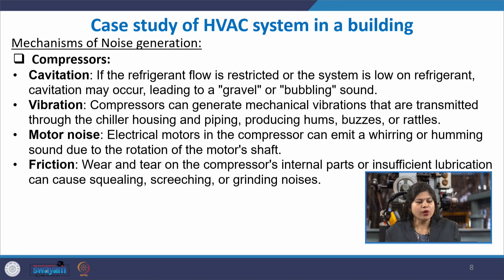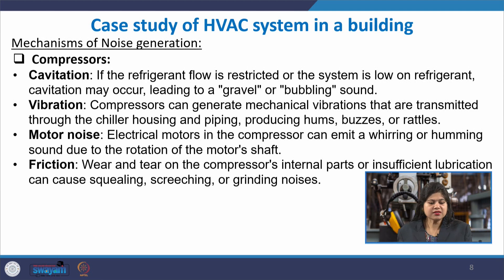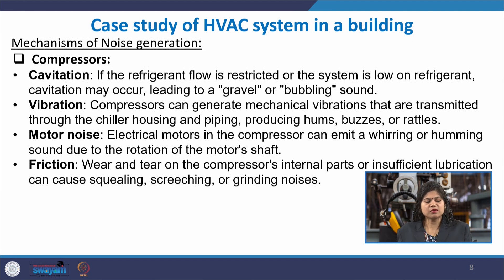Let us examine the mechanisms of noise generation in a typical HVAC system supporting big buildings. For compressors, the flow of refrigerants and pressurization of liquids are involved, making cavitation an important noise source. When refrigerant flow is restricted by dust, dirt particles, manufacturing defects, or accumulation of debris within the compressor unit, this creates more cavitation.